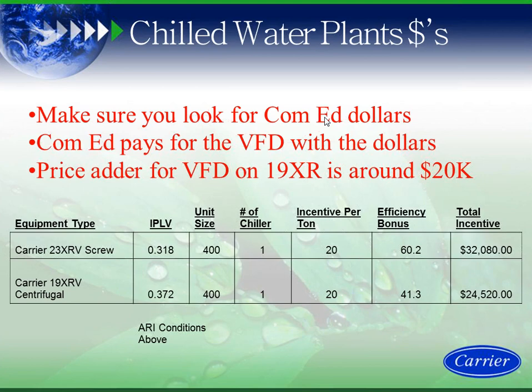And let's take a look at ComEd dollars. So ComEd will pay for the VFD on the dollar. If we look at a 23XRV, and all this data is based on ARI conditions above, I'm getting about $32,000 a year for the 23XRV. In the Carrier 19XRV, I'm saving about $24,000 a year. So again, the price adder to go to a VFD on the centrifugal is about $20,000. ComEd basically will pay for that VFD retrofit with the incentive dollars.